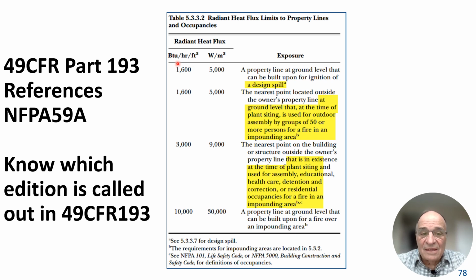And this is for a design spill. And a design spill is very much different. It's a very limited amount of LNG in most cases, unless you have a bottom penetration that has a guillotine cut and there's no internal tank valve. So we'll talk about that.